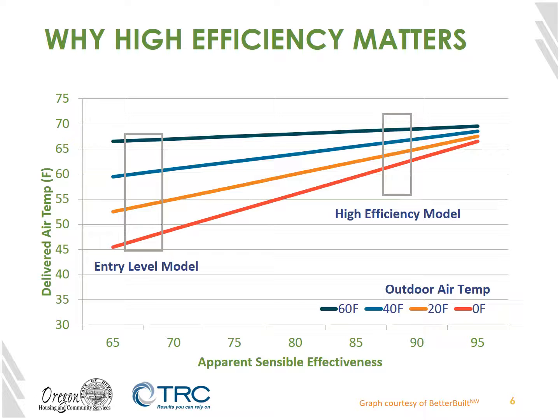So why do we say that the apparent sensible effectiveness, or the ASE, is such a big deal? Well, let's take a look at two different ASE models, an entry-level model HRV and a high-efficiency model HRV. If you look at the word entry-level model on the graph in front of you, and you see the gray box above it, that is representative of, if you go straight down to the x-axis, about a 69% ASE model. That's fairly common for the entry-level models on the market. If you go over to the right and go down from the gray box above the high-efficiency model, you'll notice that there's an ASE of closer to 87 or 88%.